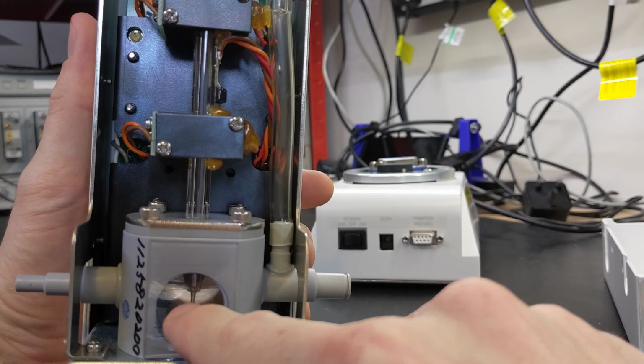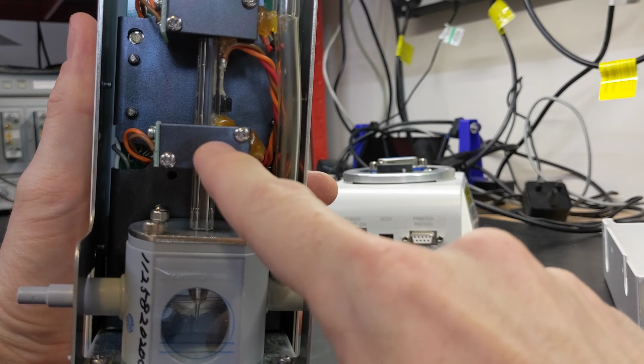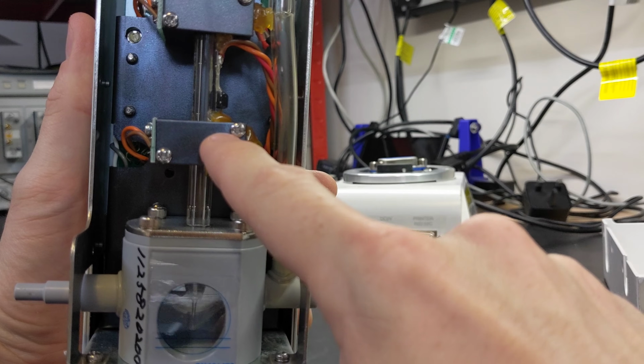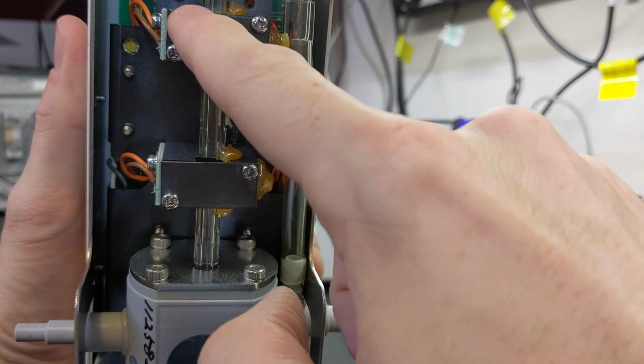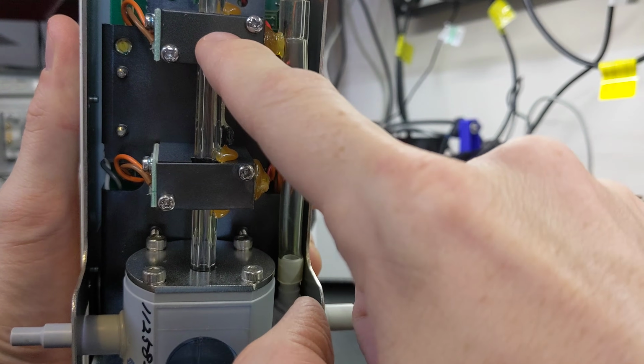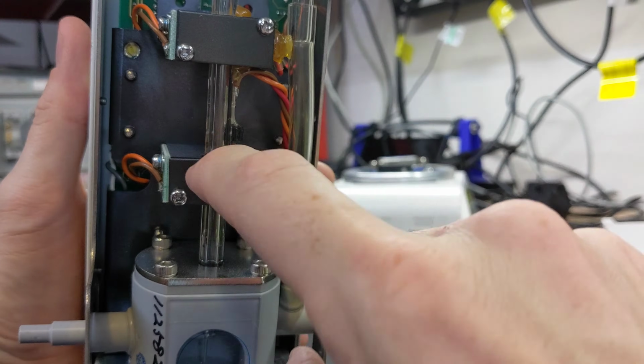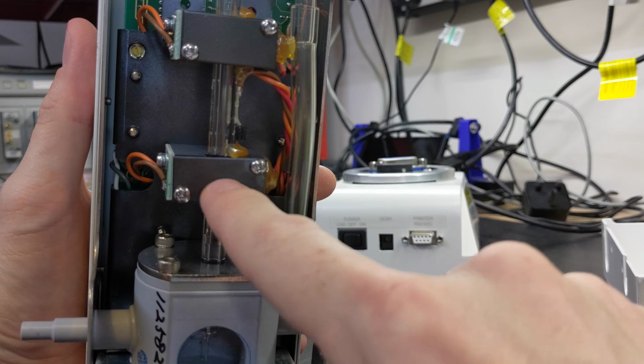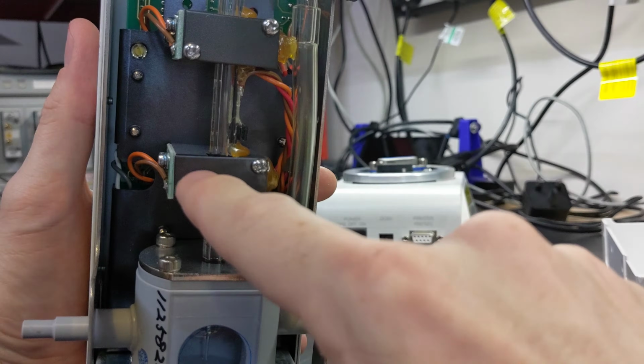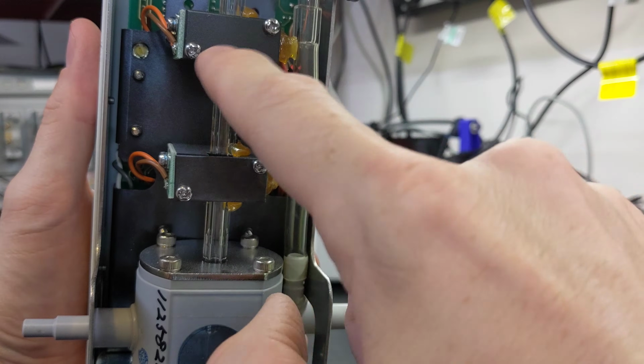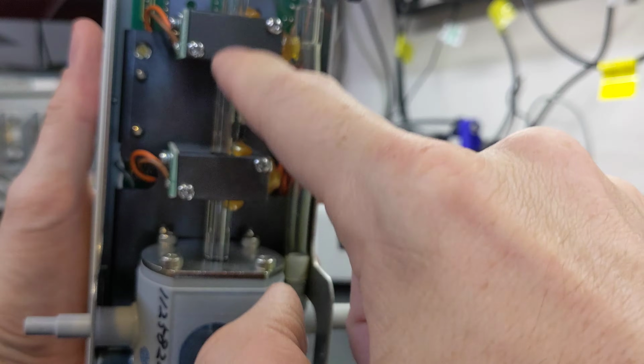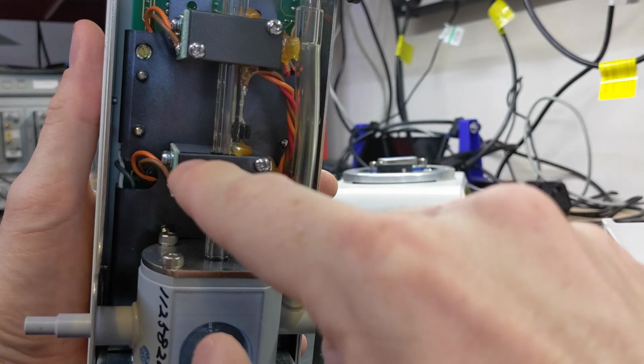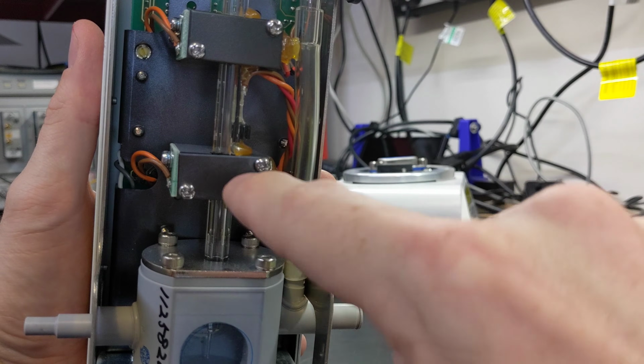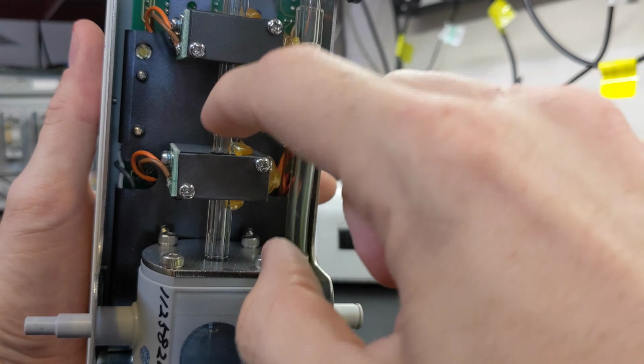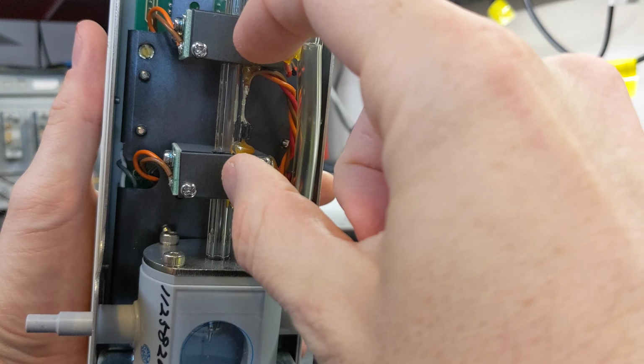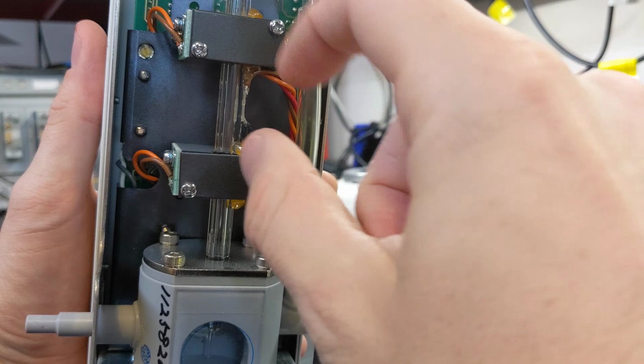Then you form a gas-tight seal because of that film bubble across the opening of this upper glass pipe. The film moves up, and the detector measures the time it crosses this location, then you move up to here and get a second detection of when the film passes back here. What's really nice is that gives you a defined volume - the distance between these two detectors is known, and the glass volume can be calibrated for. So how quickly this film moves from here to up here tells you how quickly it takes a volume of this much gas to pass through the system.